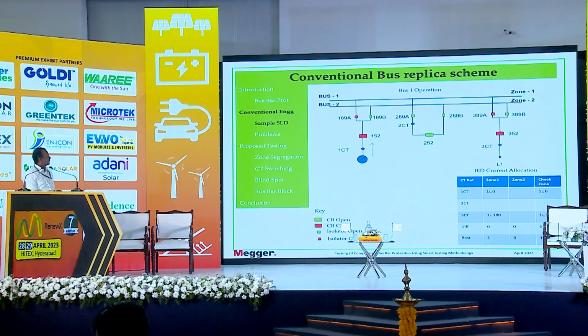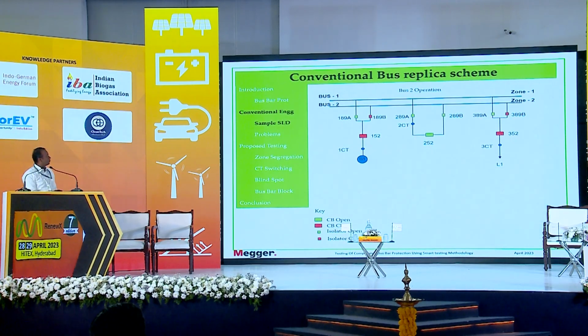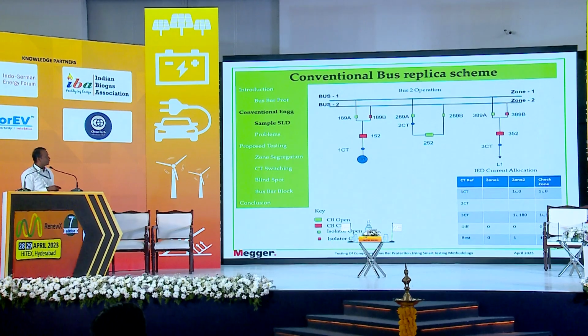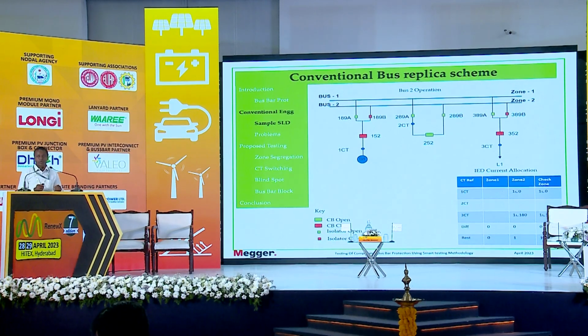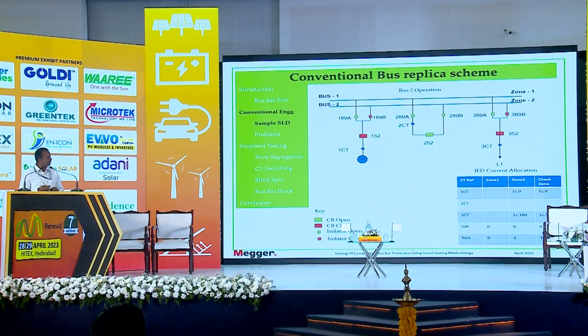So another example, if we are feeding through bus 2, this is how the current reads. So zone 2 will be reading, zone 1 is actually not reading because 89B is operated. So differential current is again 0 here.